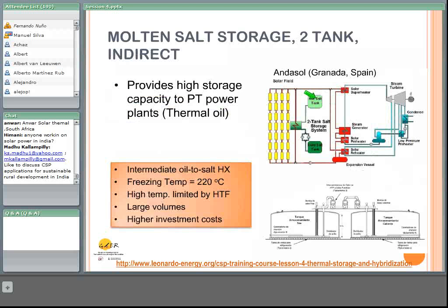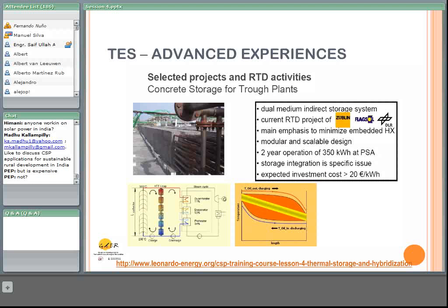There are also some advanced experiences or concepts which are being explored. For example, for trough plants, the concept of storage in reinforced concrete with embedded heat exchangers is being explored mainly by DLR together with other German companies. There have been some pilot installations at Plataforma Solar de Almería, and the expected investment cost will be in the range of 20 euro per kilowatt hour. A rough idea about the cost of the molten salt storage for a parabolic trough plant is that it can be in the range of 25 euros per kilowatt hour, all equipment and molten salts included.